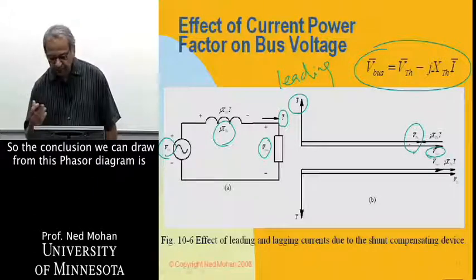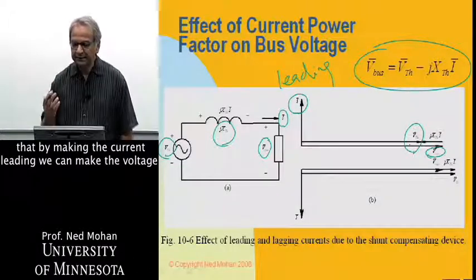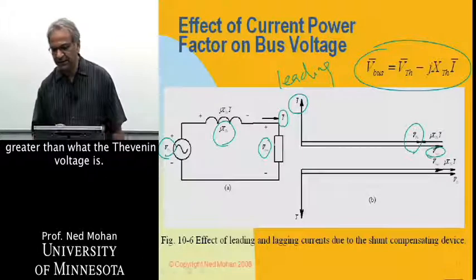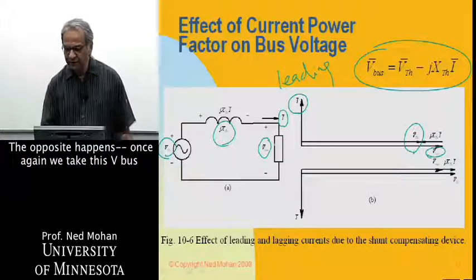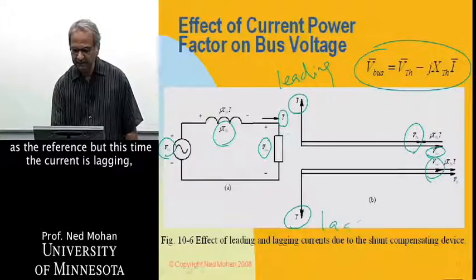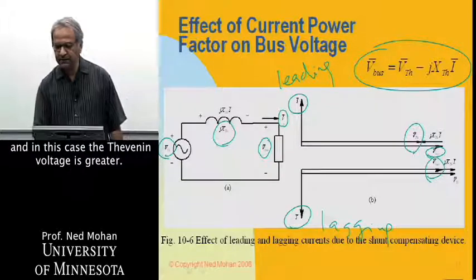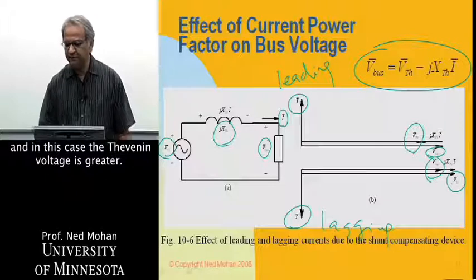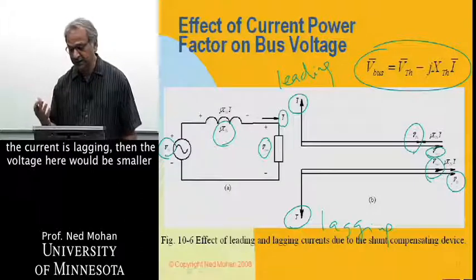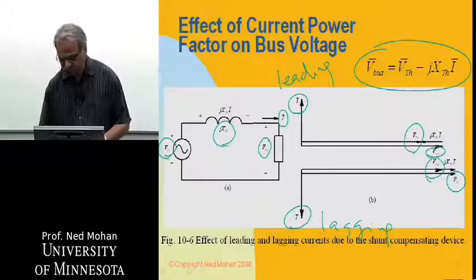The conclusion we can draw from this phasor diagram is that by making the current leading, we can make the voltage at this bus greater than what the Thevenin voltage is. The opposite happens when the current is lagging the bus voltage — in that case, the Thevenin voltage is greater, meaning the bus voltage would be smaller in magnitude compared to the Thevenin voltage.